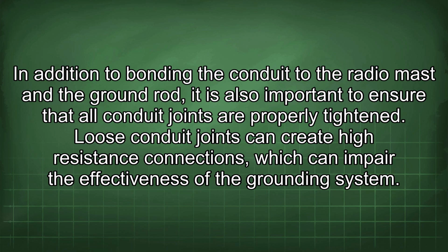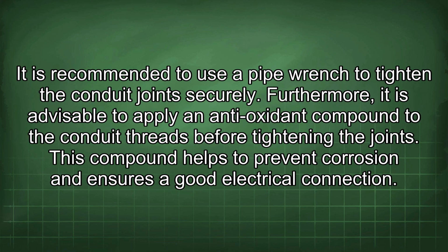In addition to bonding the conduit to the radio mast and the ground rod, it is also important to ensure that all conduit joints are properly tightened. Loose conduit joints can create high resistance connections, which can impair the effectiveness of the grounding system. It is recommended to use a pipe wrench to tighten the conduit joint securely. Furthermore, it is advisable to apply an antioxidant compound to the conduit threads before tightening the joints. This compound helps to prevent corrosion and ensures a good electrical connection.